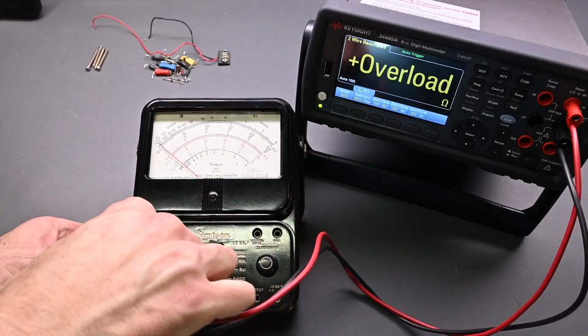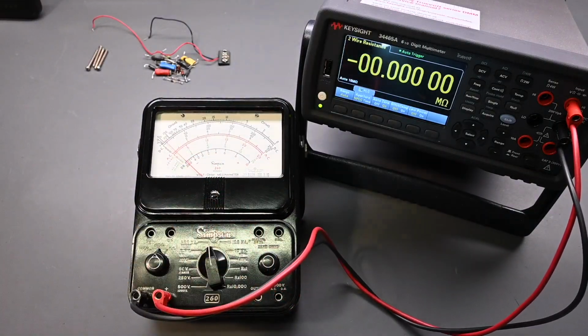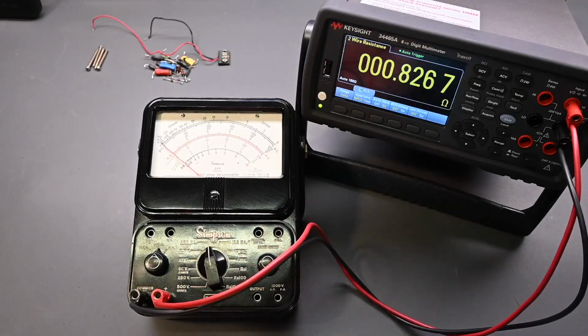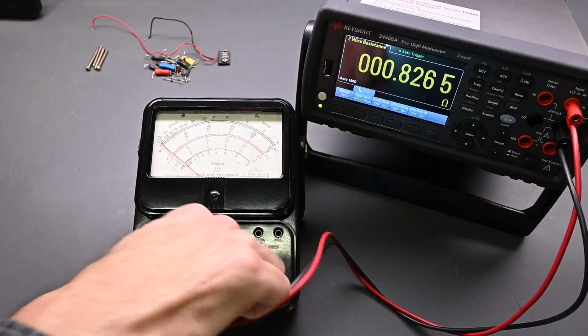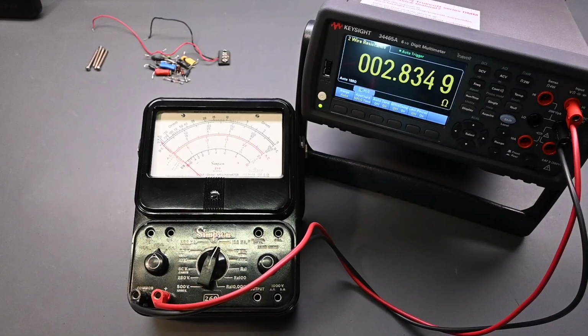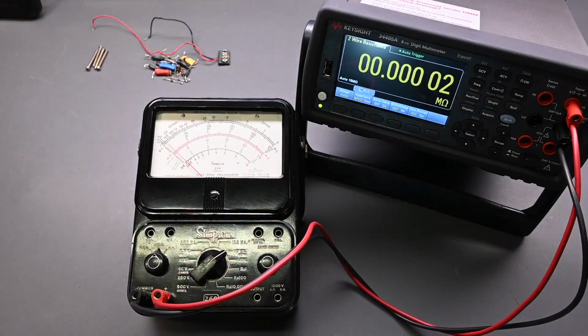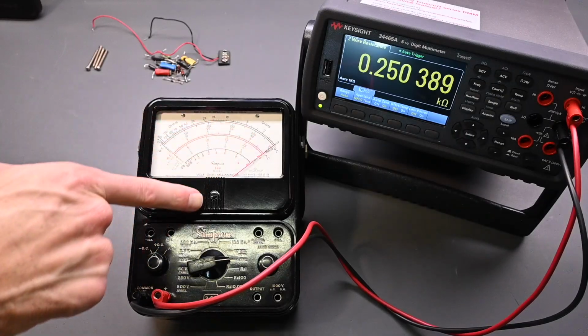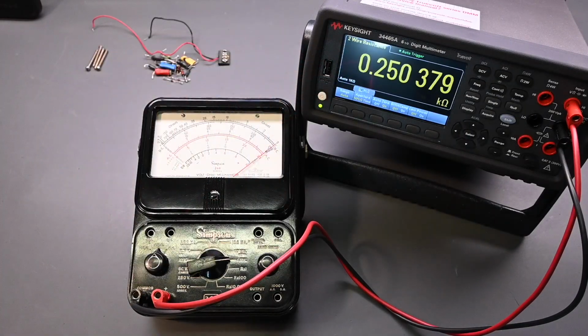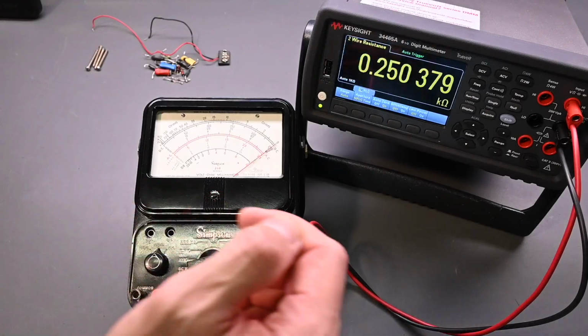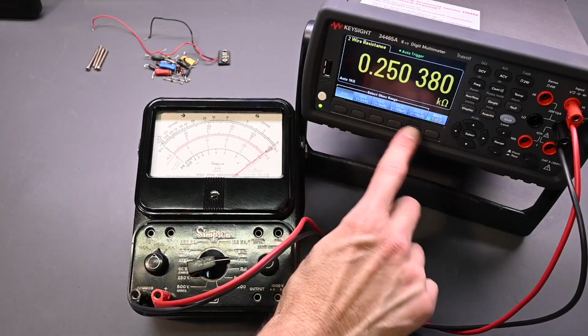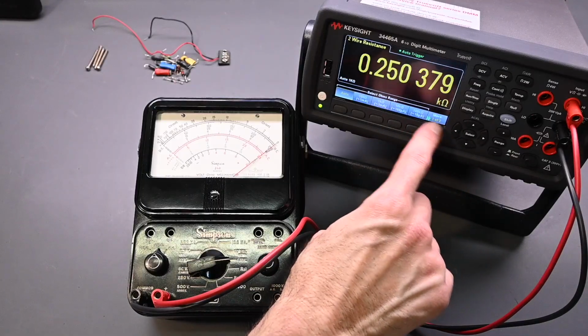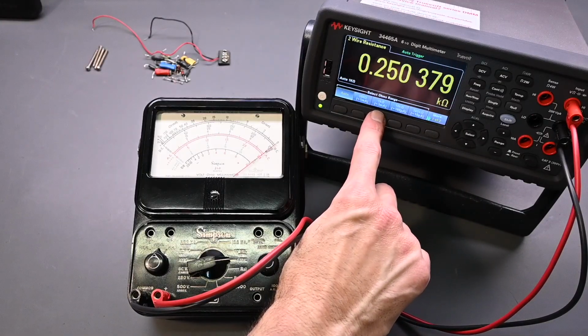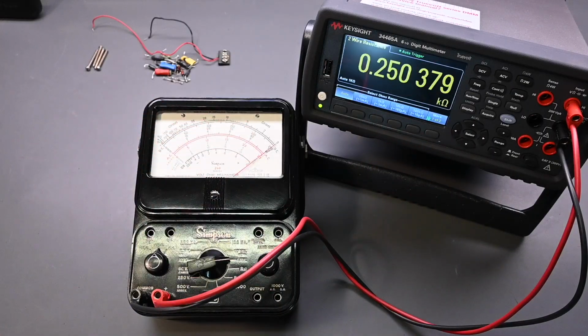If I go back over here, go all the way around to the resistance ranges, so 500 milliamps, perfect. No problems there, that looks reasonable. 100 milliamps, yep, 2.8 ohms, over that, perfect. 10 milliamps, yep, 25 ohms, 25.2, that looks reasonable. And 1 milliamp. Actually, we can see we have a full scale deflection on the meter right at 1 milliamp and 250 ohms, and that looks correct. Actually, if we go over here to this setting, you can see right here, this is in the 1,000 ohm, and right here it says it's about 1 milliamp that it sources, so exactly what this is reading, so it makes sense. Perfect.